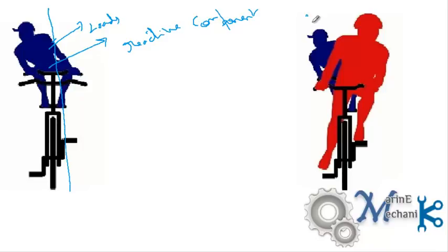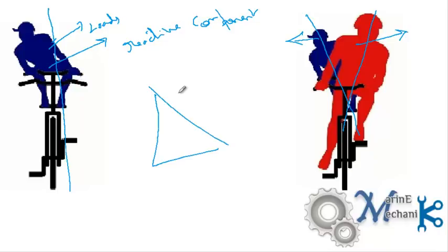Since the load is leaning this way, the generators will start to lean this way. What does that mean electrically? With the power triangle, as we all know, this is the KVA section, this is the KVAr, and this is the KW. So as the KVAr load increases, the kilowatt load reduces just to maintain the same KVA.